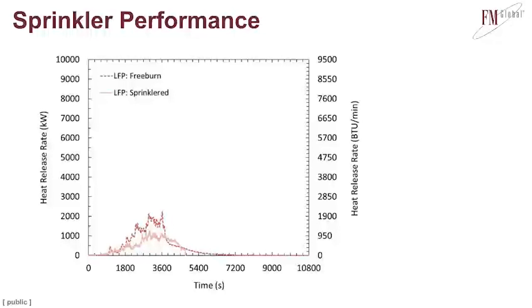Now, I do have some data just to try to build out a little bit of background as to how we developed, or we're looking at developing, protection guidance for these. It's important to remember here that the iron phosphate system, which is the two data traces you see right now, was 83 kilowatt hours, and the NMC system is 125. So there is a difference in the amount of available energy between these two systems.